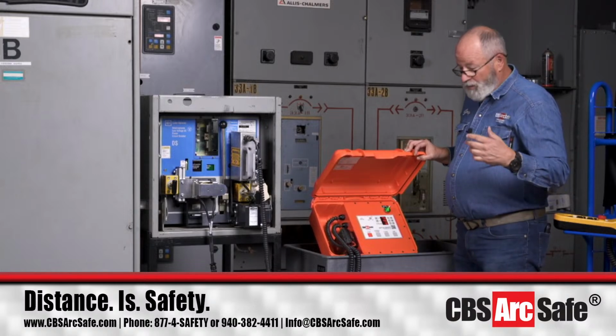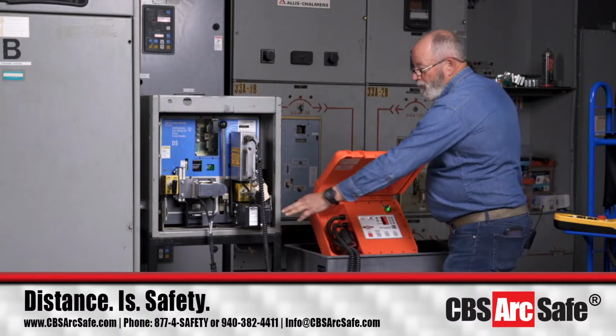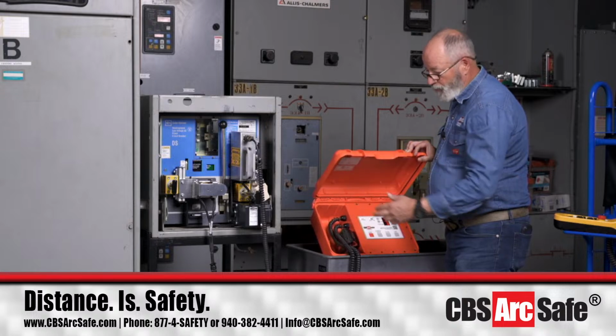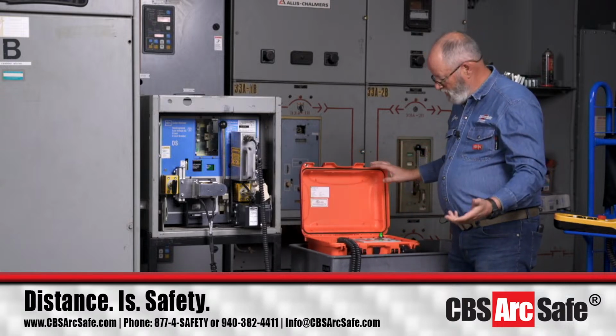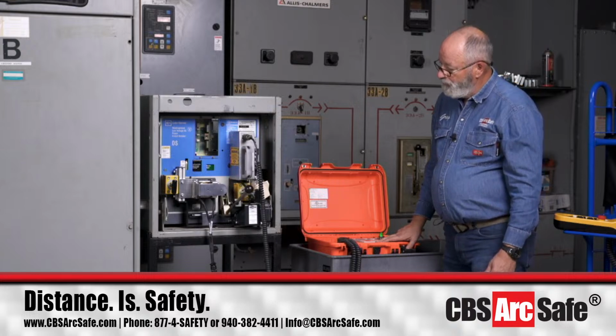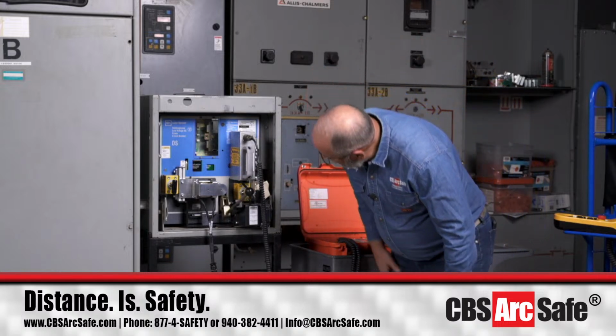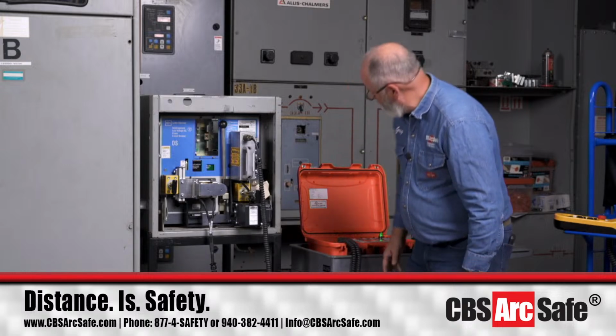So we had to, this is the button that operates the motor. This is the buttons that operate the solenoids. So some breakers will charge and close on one operation, so that's the reason it's labeled charge close. And all we do now is we push the button one time. And it should go up. All right, I may have to increase it just a little bit because it did not charge the spring.